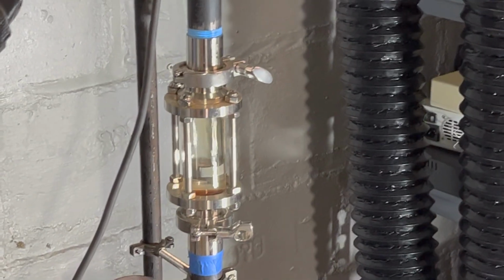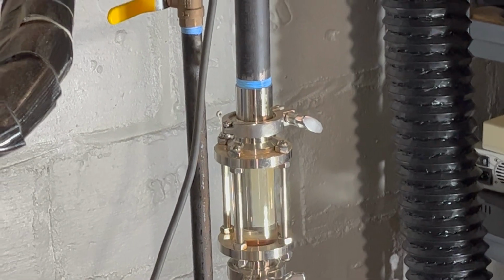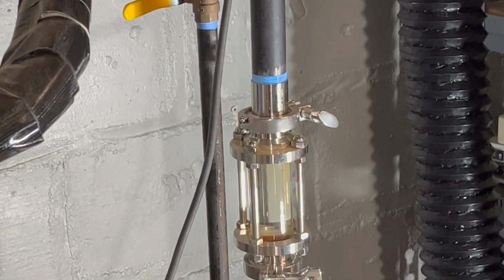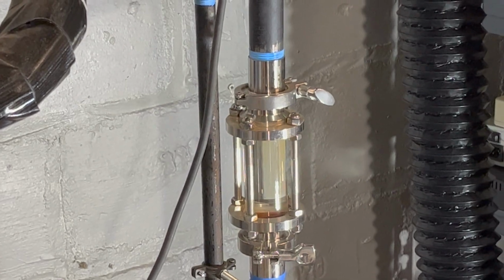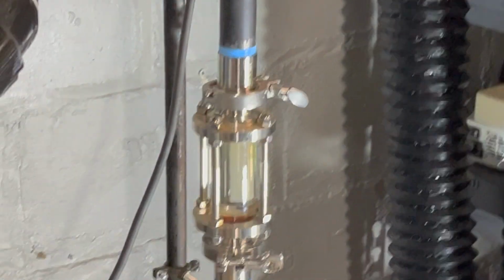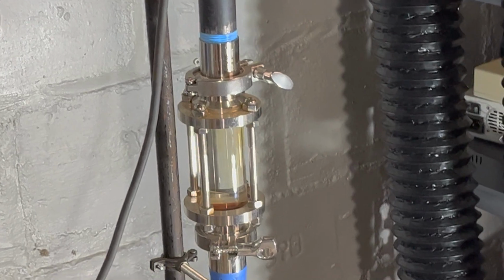If I close it further, I can make it go higher. Look, there it goes. It's going higher now. It's somewhere up beyond, up there, it's right at the top of the glass. It's like equilibrium. It's right there. We saw it reappear. There it is. See that? It's right there. If I close this valve, I know from experience, this valve, okay, not the useless equalizer valve that doesn't do anything. If I close this valve, of course, we're going to see a big difference in pressure.